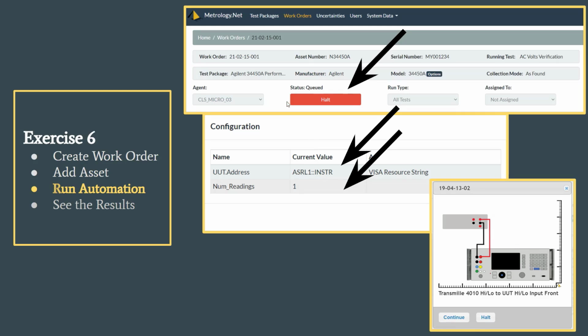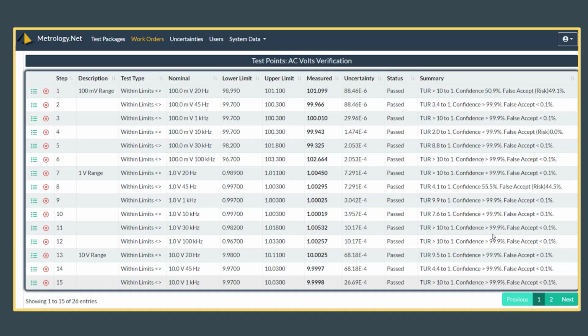I get this little halt button up here where it says this is the status and this is halt. It's a halt button. It doesn't mean that the program has stopped. It's a button that's up there that lets you halt it. I've had some people come in and say that it's not running because the halt button is up, and I'm like, no, it's a status. So inside of here is where you see the current status, and then the button comes up as well as giving you your connection messages.